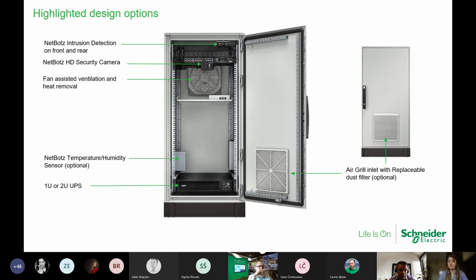In this scenario, there's a white box, which is actually an EcoStruxure gateway placed on the shelf, allowing us to connect to EcoStruxure IT cloud-based software so customers can remotely monitor the micro data center and assets inside it. We also have fan-assisted ventilation, with fans at the back of the rack and vents in front, providing that air draw-through approach.